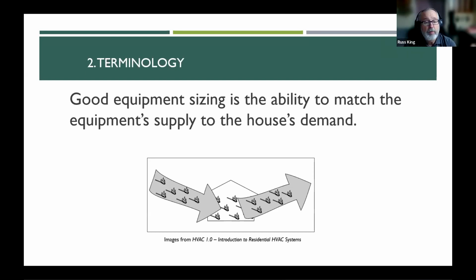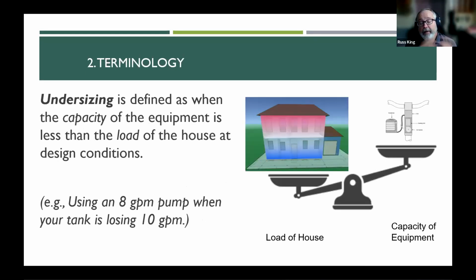And you might say, well, where's the harm in that? It's like putting a bigger engine in your car than you really need, right? Well, the harm is that it can make your car run very poorly by putting too big of an engine in it, and it can make it run very expensively, right? Not very good gas mileage and stuff like that. Same thing for a house. So sizing the equipment to the load is very, very important for efficiency, and hopefully I can demonstrate to you for comfort as well. So undersizing is when the load of the house is greater than the capacity of the equipment. Your equipment's too small for the load. It can't keep up, okay?